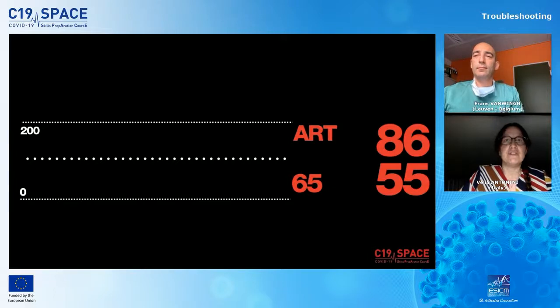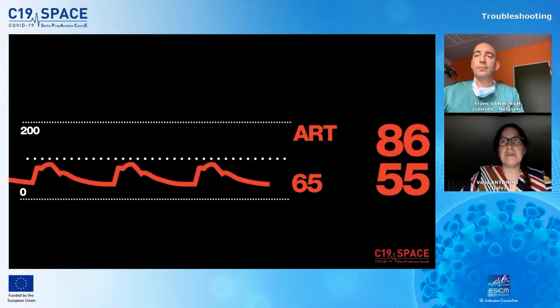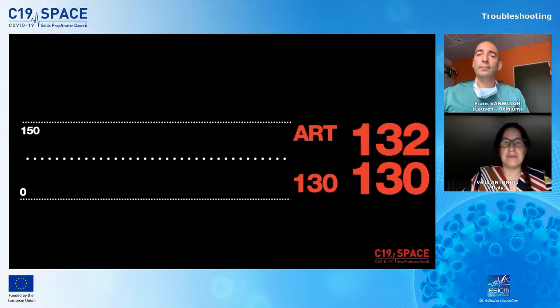If the range is too high, the wave is going to appear attenuated. You need to adapt the range to the pressure of this particular patient, in this particular moment, and you need to modify the range as and when needed. Be ready.